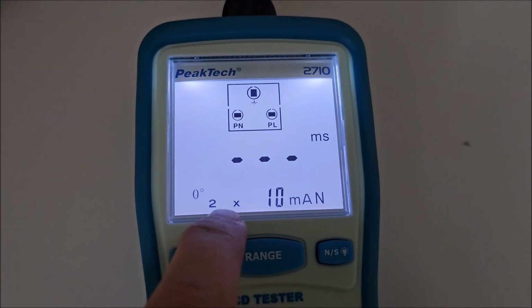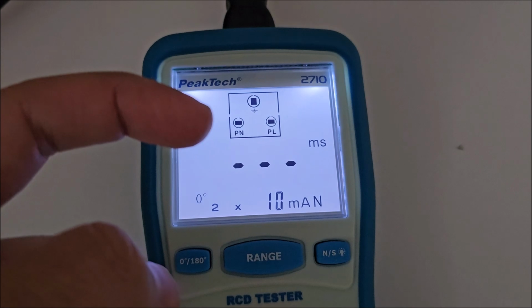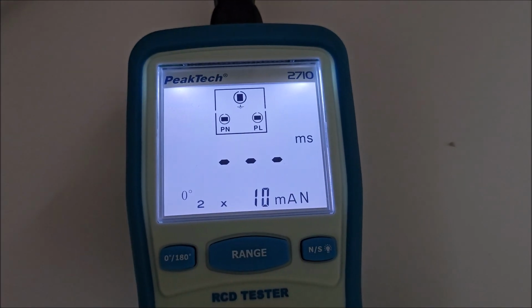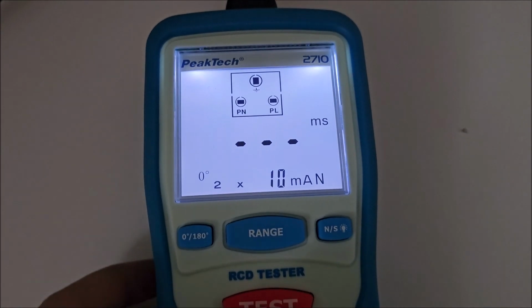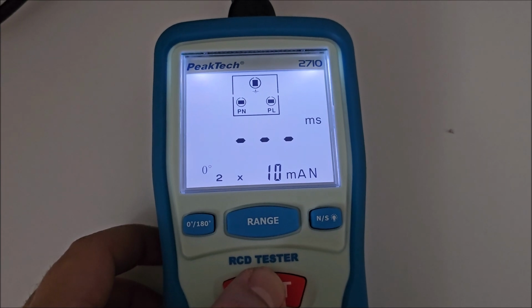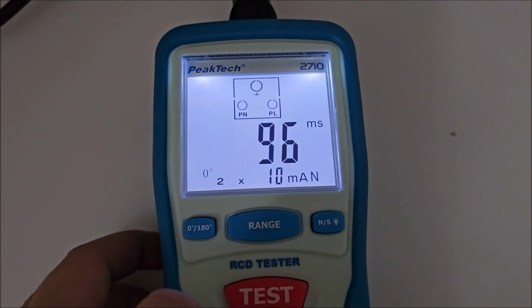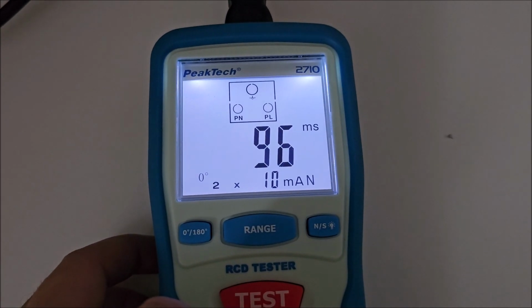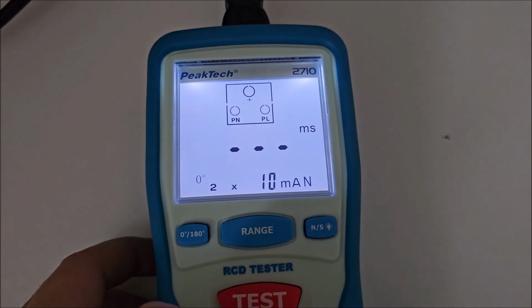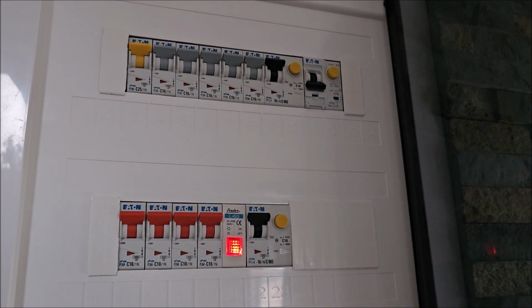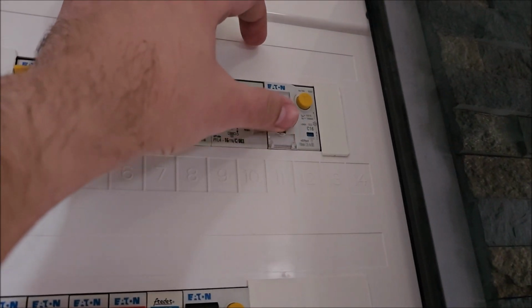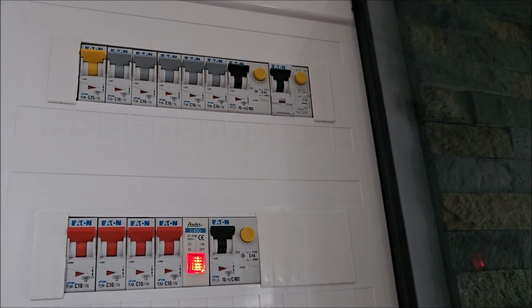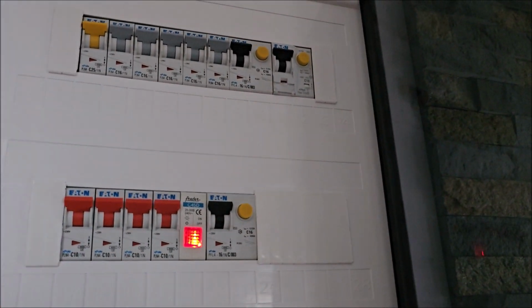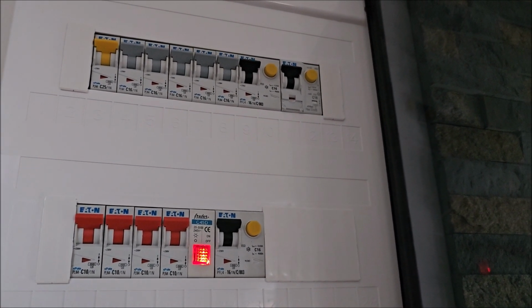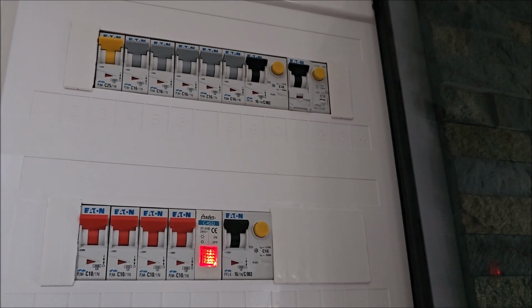10 milliamps times 2, 20 milliamps. The outside one shouldn't be tripping, but the inside one maybe trips faster at a bit higher current. Let's see. Yep, it trips faster, but still much slower than the outside one, if there was any question about it. So even at 20 milliamps, this one is still doing its job. And the outside one, it's below the 30 milliamps and it's not tripping.